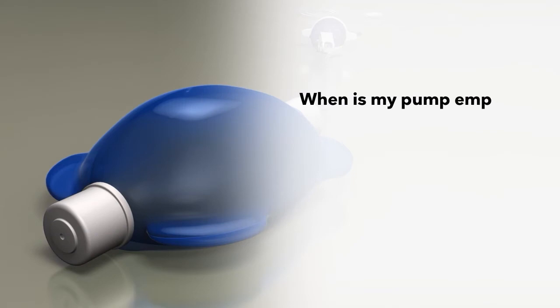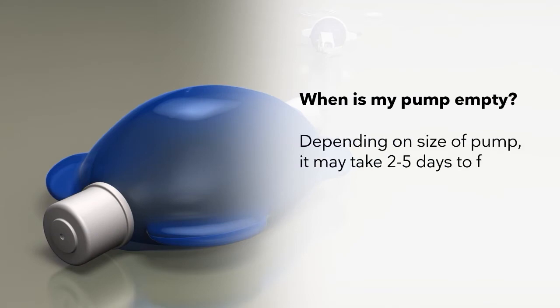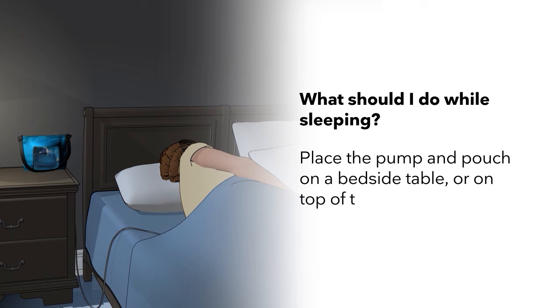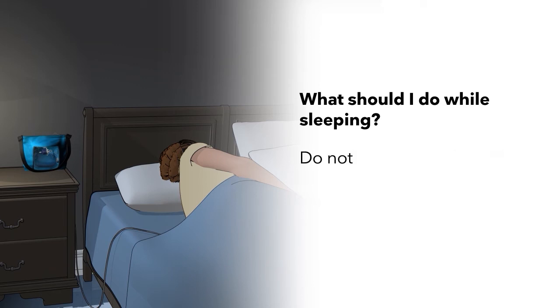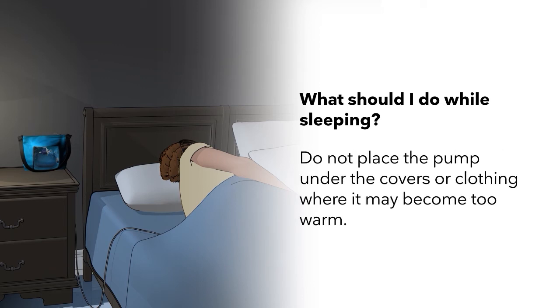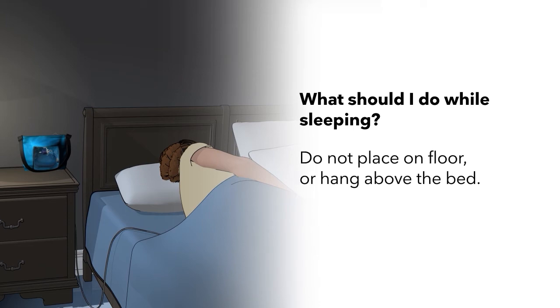When is my pump empty? Depending on size of pump, it may take 2 to 5 days to fully deflate. What should I do while sleeping? Place the pump and pouch on a bedside table or on top of the covers. Do not place the pump under the covers or clothing where it may become too warm. Do not place on the floor or hang above the bed.